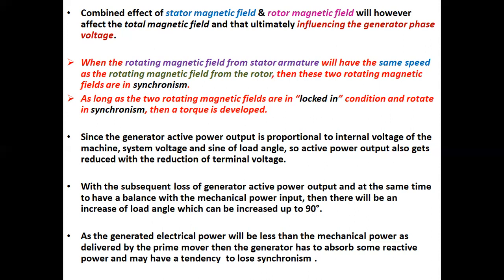With the subsequent loss of generator active power output, and at the same time to have a balance with the mechanical power input, there will be an increase of load angle, which can increase up to 90 degrees. As the generated electrical power will be less than the mechanical power as delivered by the prime mover, the generator has to absorb some reactive power and may have a tendency to lose synchronism.